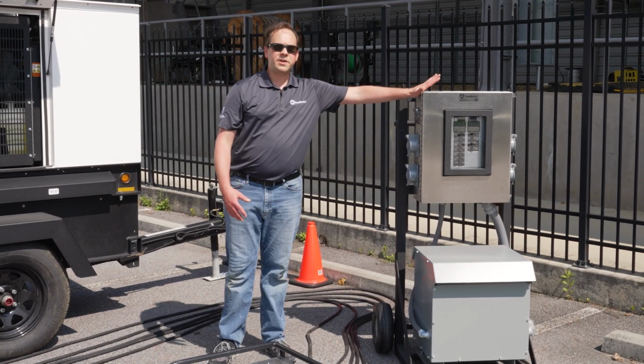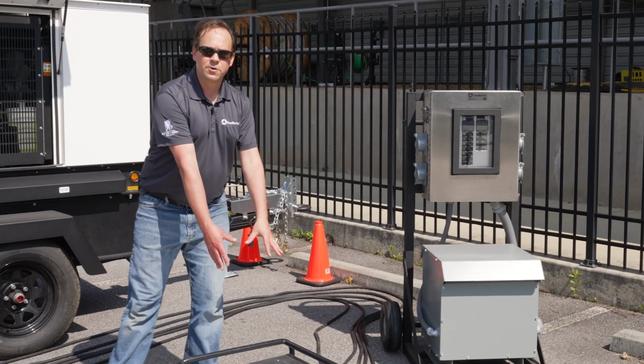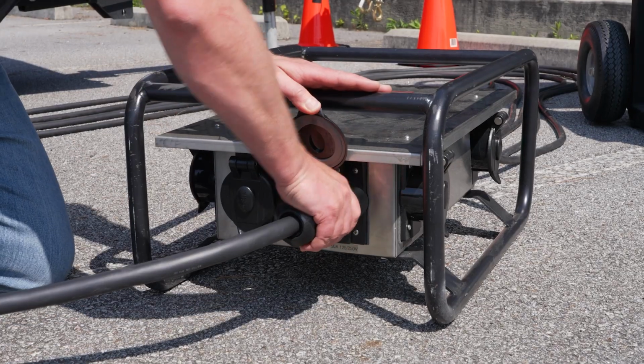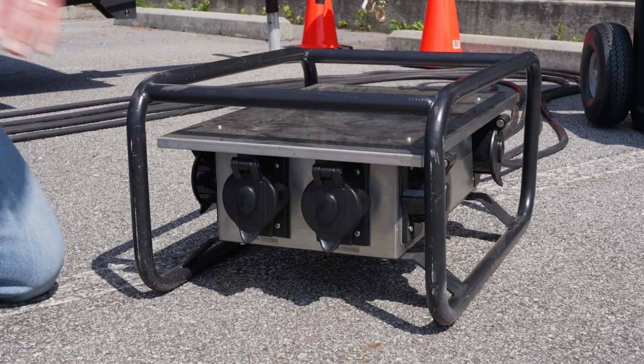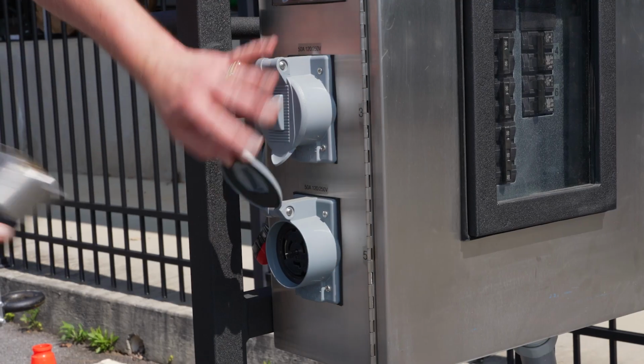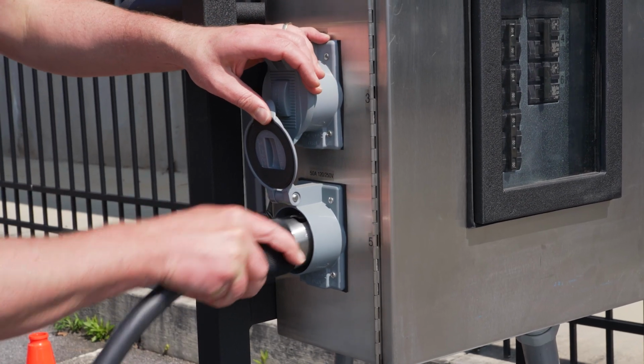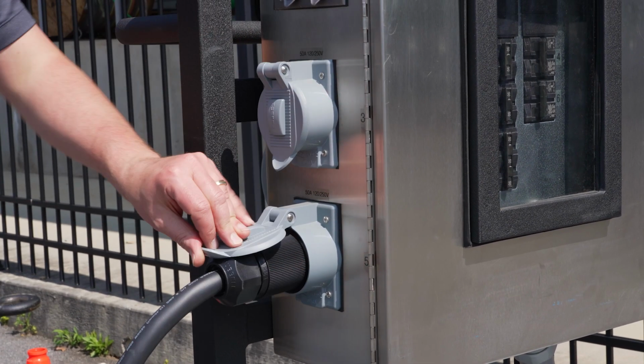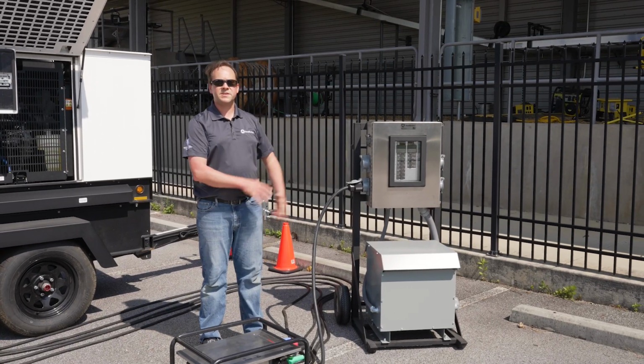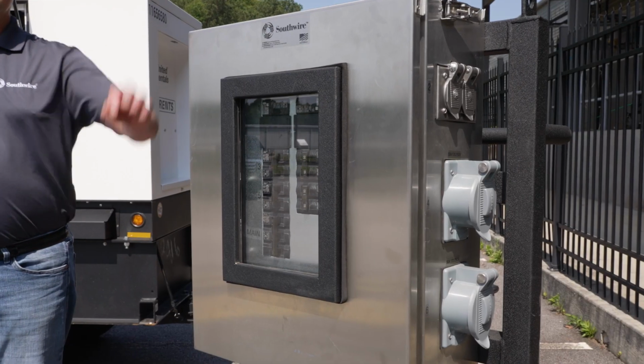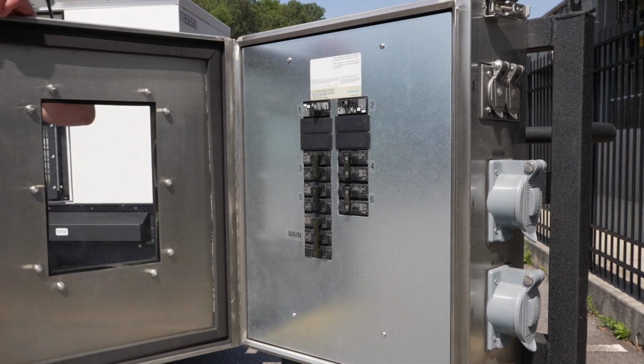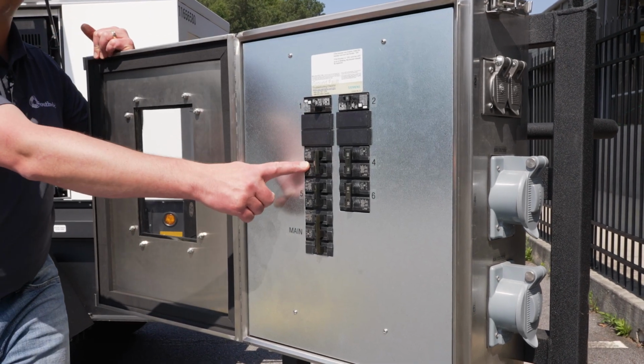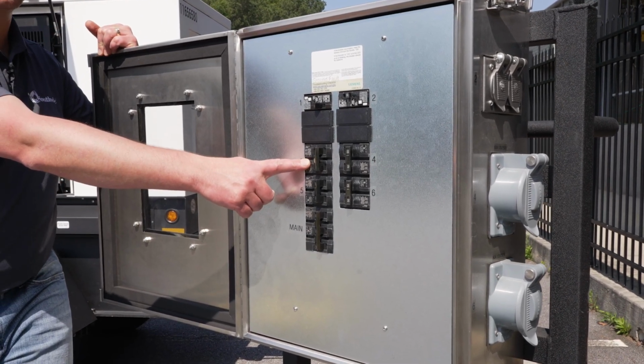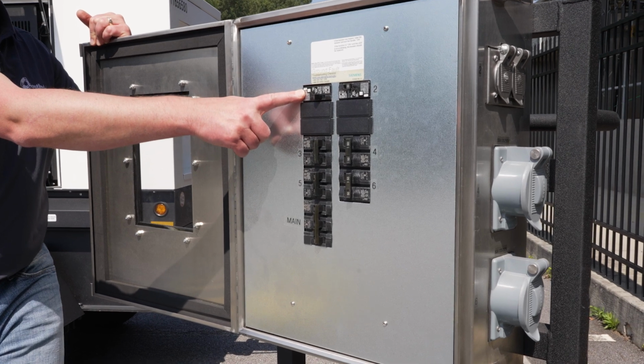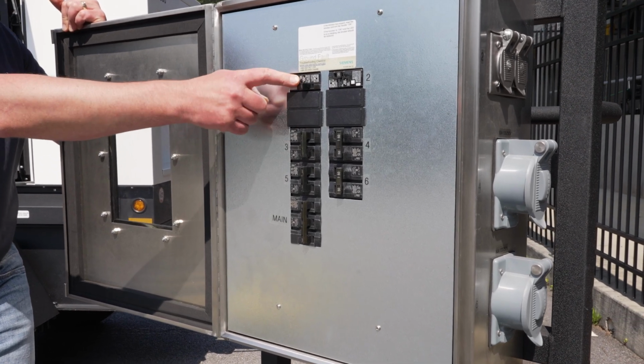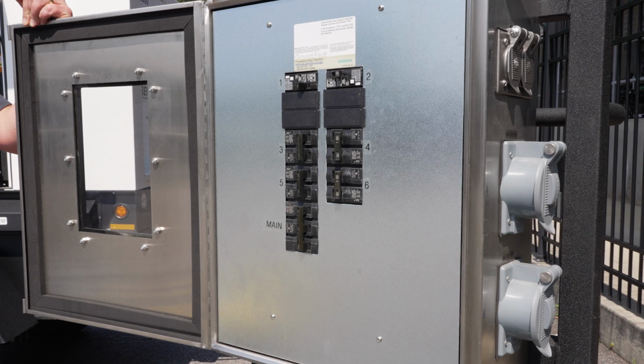So this panel here is basically the same as the stainless steel box on the ground. So instead of connecting to this, if my cart were connected to the generator, I could connect this wiring device right here, and I'd have the same access to that temporary power system downstream. So here inside of these stainless steel panels, we have the 50 amp circuit breakers that provide that overcurrent protection, as well as 20 amp circuit breakers for some convenience receptacles that include that GFCI mandated by OSHA.